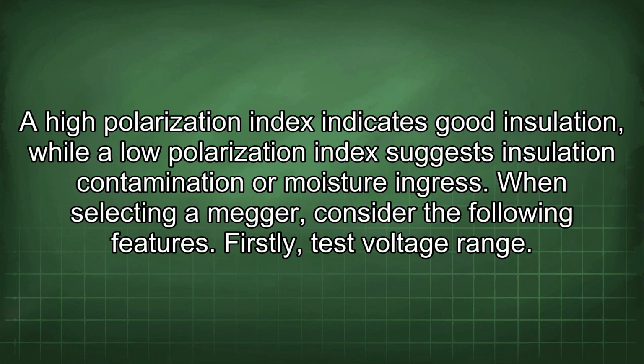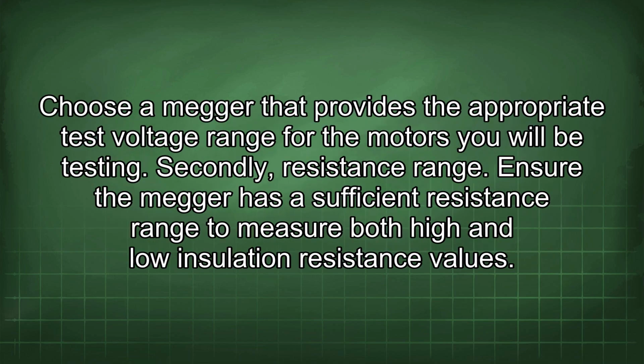A high polarization index indicates good insulation, while a low polarization index suggests insulation contamination or moisture ingress. When selecting a Megger, consider the following features. Firstly, test voltage range. Choose a Megger that provides the appropriate test voltage range for the motors you will be testing. Secondly, resistance range. Ensure the Megger has a sufficient resistance range to measure both high and low insulation resistance values.